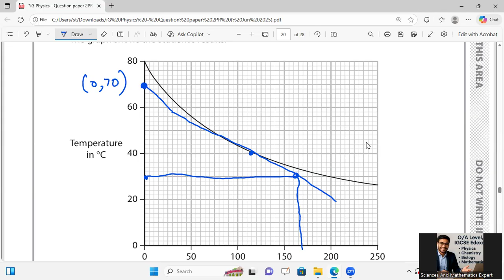Then go for gradient calculation. M is equal to y2 minus y1 over x2 minus x1. Then you can use this formula for calculation of your rate. So if you go for its calculation, then I will say 70 minus 30 is 40, and 0 to 165, so it is 40 over 165, and it is with the negative temperature coefficient, and it will be approximately 0.2 to 0.3 degrees centigrade per minute will be your rate of change for this question.